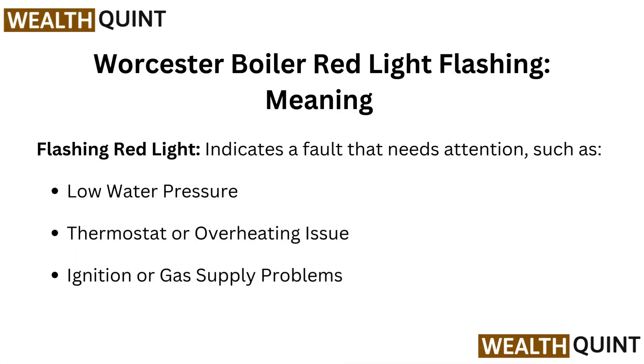Worcester Boiler Red Light Flashing meaning: a flashing red light indicates a fault that needs attention, such as low water pressure, a thermostat or overheating issue, or ignition and gas supply problems.